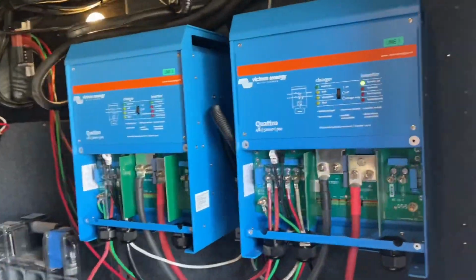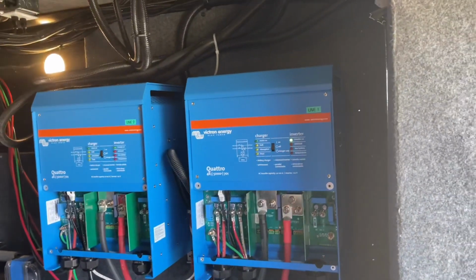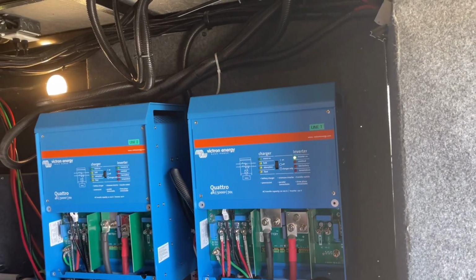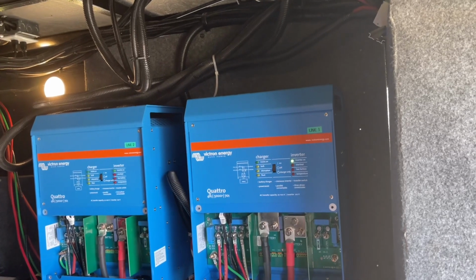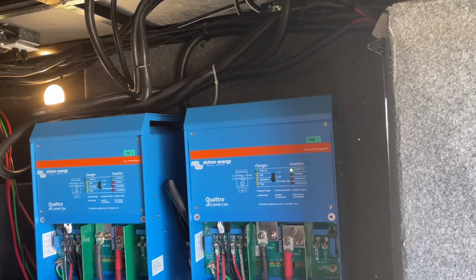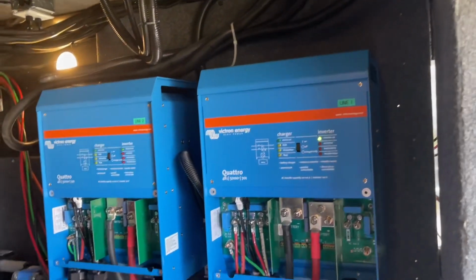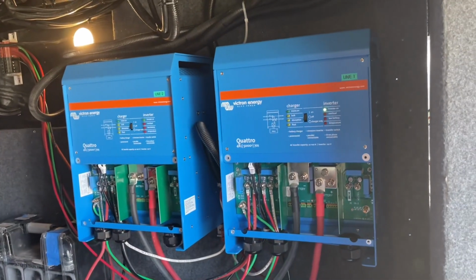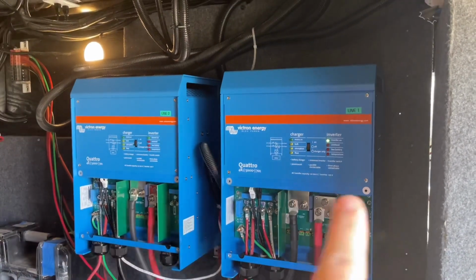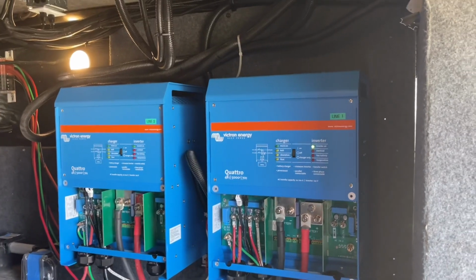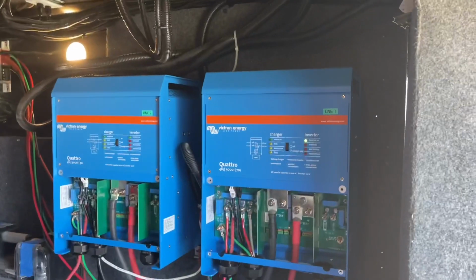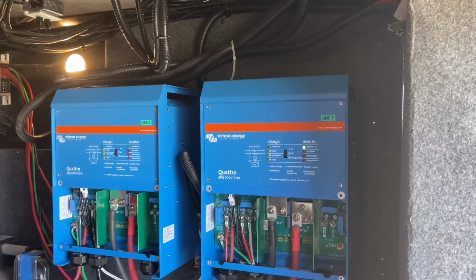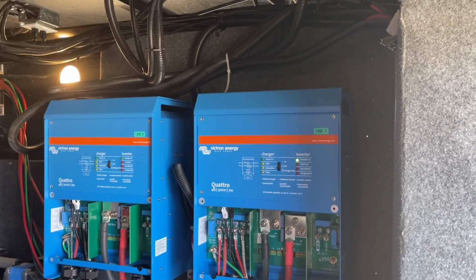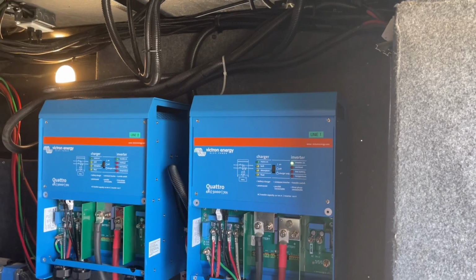You can see the panels are still off, but here's my two Victron Quattro 48 volt 5 kVA each inverters. So I have up to 10 kVA, or approximately 8,000 watts if I were to perfectly balance line 1 and line 2. I did this configuration because the mini split is a 240 volt appliance, which is really unusual for an RV to have an actual 240 volt split phase requirement.